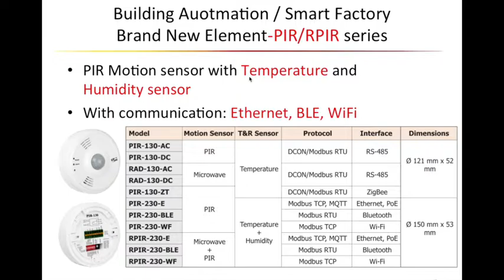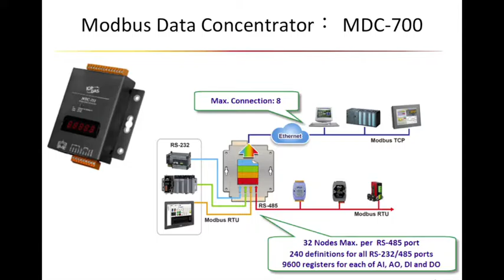Due to the experience that we learned from projects, we realized that the communication speed was slow and we needed a tool that can boost up RS485 speed. That's the reason that we developed the MDC series. The conventional approach is to read back the data from the meters one by one via RS485. However, the speed will be quite slow. The speed bottleneck of this system is that the speed of the RS485 itself is not fast enough, so even if the performance of the PC is enhanced, the speed problem still cannot be solved.